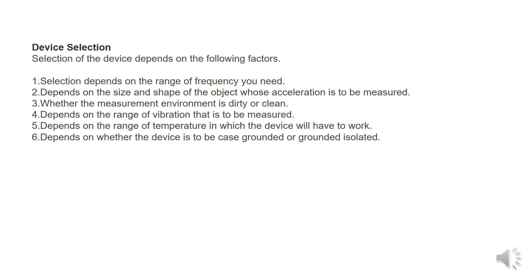If we are going to select, the following factors we have to consider during selection procedure of an accelerometer. Selection depends on the range of the frequency we need, depends on the size and shape of the object whose acceleration is to be measured, whether the measurement environment is dirty or clean, and depends on the range of the vibration that is to be measured.